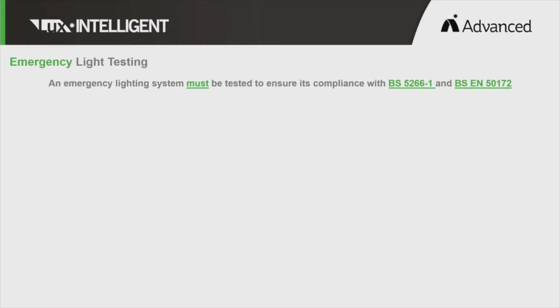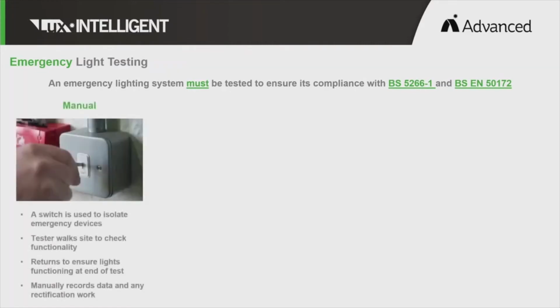In basic terms, there are three ways to test your emergency light system. The manual way, with test key switches, where a competent person manually isolates the luminaires on site, does a visual check of all lighting, records the results and failures, and then creates a work schedule to rectify any issues found. This is time consuming, needs to be done out of hours, and is prone to human error.